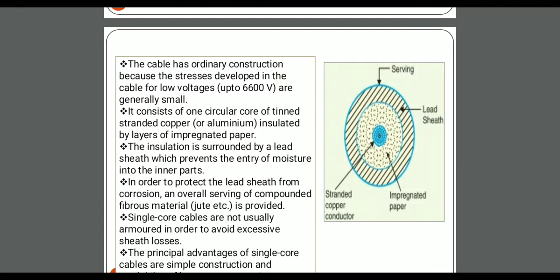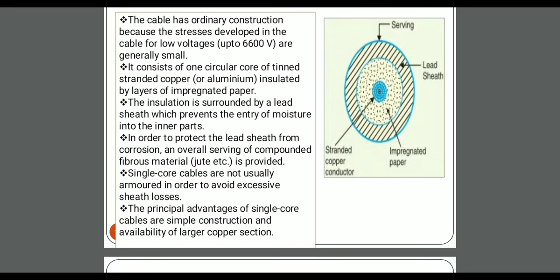It has an ordinary construction because the stresses developed in the cable for low voltages are generally small. This is circular in shape: stranded copper, impregnated paper, lead sheath, and serving. This is the structure of a single core cable. The main advantage of a single core cable is that it is very simple to construct, and there is the availability of a large copper section.